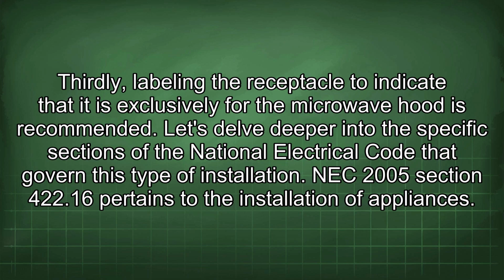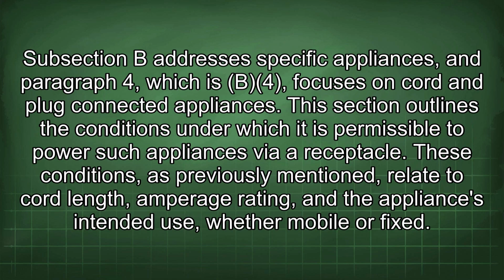Let's delve deeper into the specific sections of the National Electrical Code that govern this type of installation. NEC 2005 Section 422.16 pertains to the installation of appliances. Subsection B addresses specific appliances, and paragraph 4, which is B4, focuses on cord and plug connected appliances. This section outlines the conditions under which it is permissible to power such appliances via a receptacle. These conditions, as previously mentioned, relate to cord length, amperage rating, and the appliance's intended use, whether mobile or fixed.